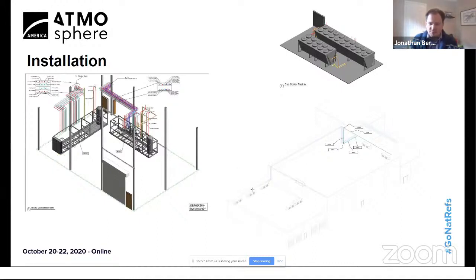This made the individual runs very small, and we were able to locate those runs inside the building, which worked well because they could construct the building and then we just put the piping in place once ready. Also, by having racks, we were able to manufacture and test those off-site, which worked really well with the tight schedule we had to deliver on.